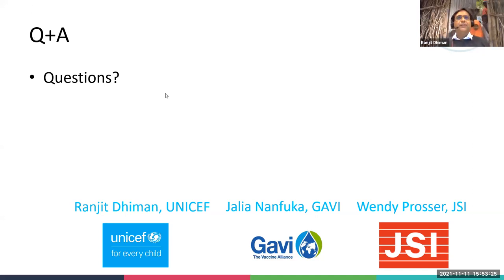Okay. So mapping of cold rooms: cold rooms are large and there are two or more cooling units in a cold room, so the placement of vaccine is essential, and it really depends on load of the cold room, where the hot spots are, where the cold spots are. And that's where mapping comes into the picture. To make sure that when a cold room is installed, both units are cooling adequately, and none of them is dropping the temperature below desired. And in different situations, in loaded and in empty situations, that's where mapping is essential for cold rooms.